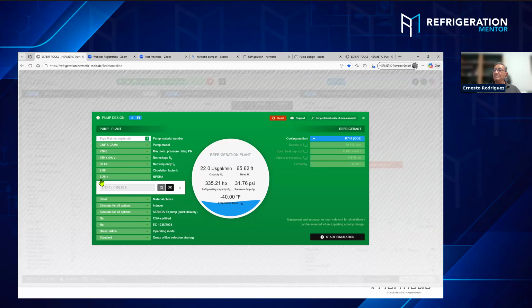In this situation, if we have a drop in the NPSHA, net positive suction head, and we get too low on our chart, that could cause cavitation. Is that right? Yes, exactly. I size it, for example, at 5 feet, which is 1.5 meters. It means the safety minimum of the pump is going to be 1.5 meters.